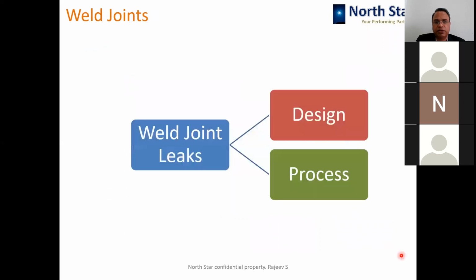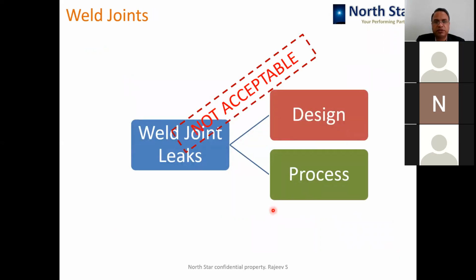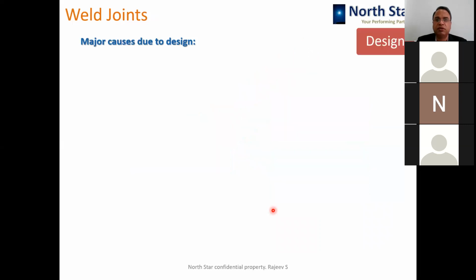Now coming to welding joints: weld joints can leak because of design and because of process. Weld leak joints are most difficult to attend to at site and they cost heavily. So any transformer leaking at a welding joint is not acceptable if you really want to control your warranty cost.